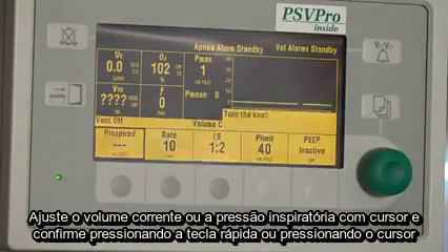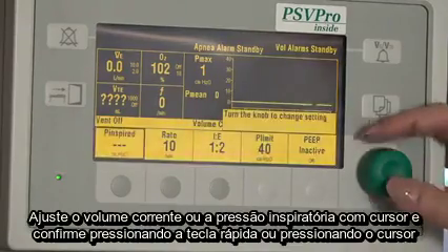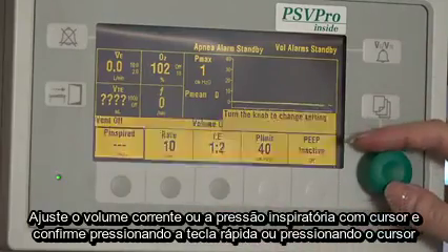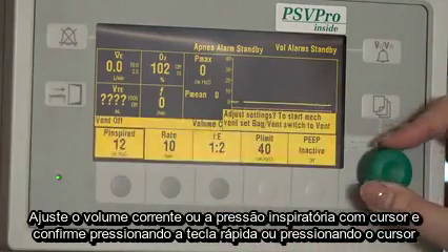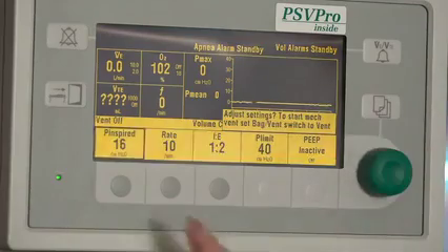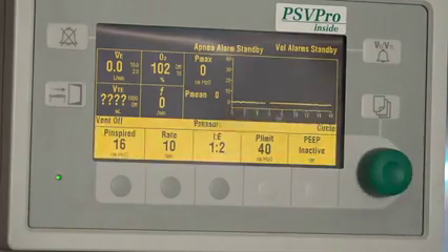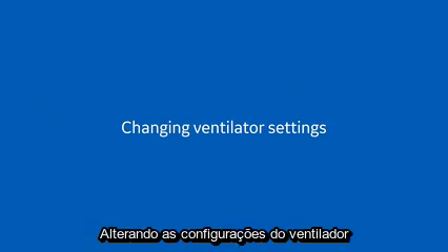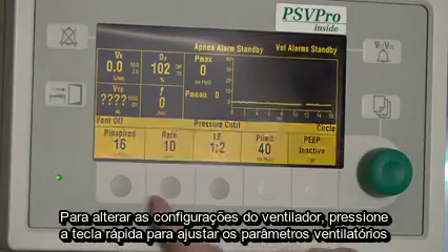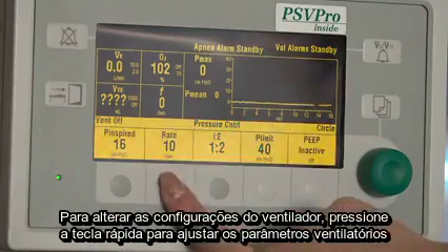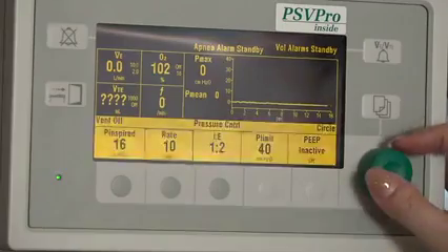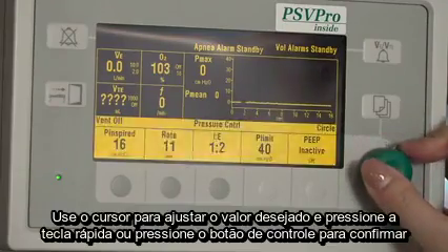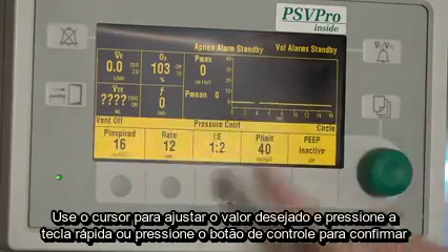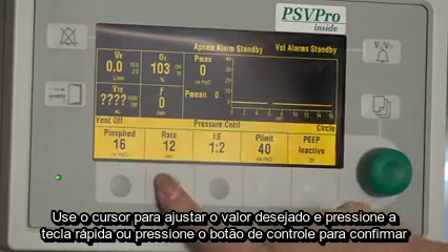Set the tidal volume or inspiratory pressure using the COM wheel and confirm by pressing the hard key or by pressing in the COM wheel. To change the ventilator settings, press the hard key for the ventilation setting to be adjusted. Use the COM wheel to adjust the desired value and press the hard key or press in the COM wheel to confirm.